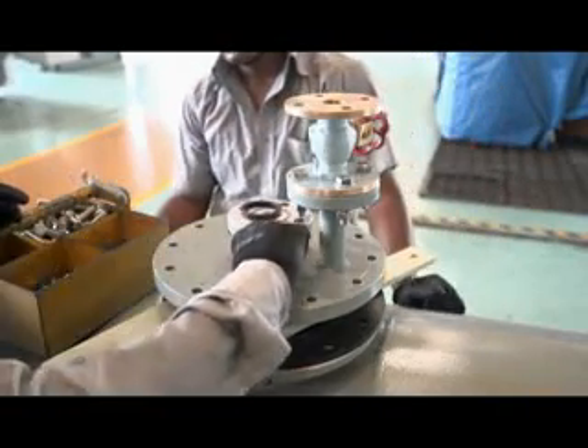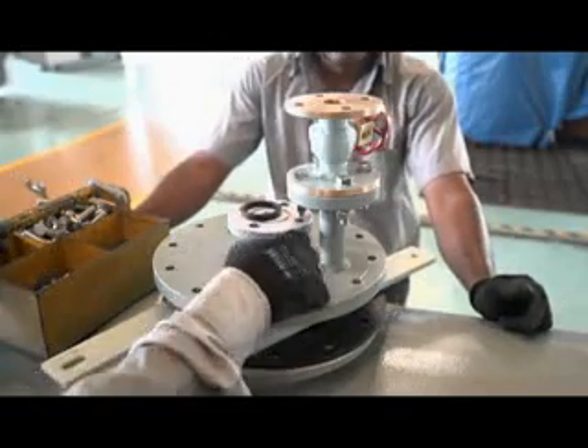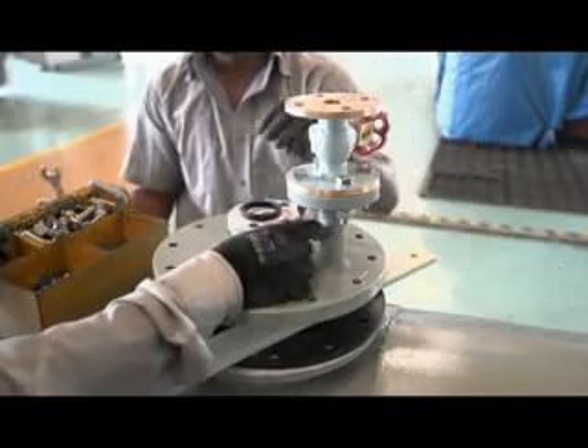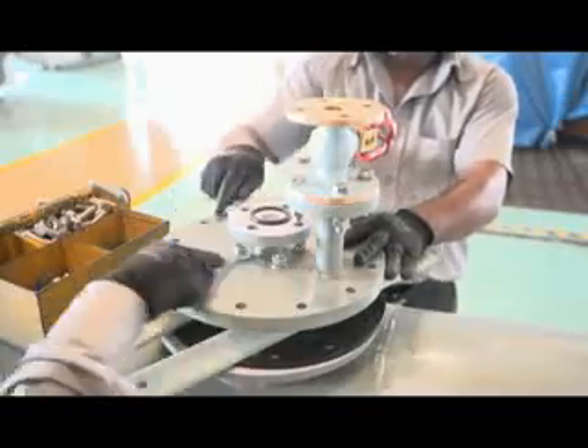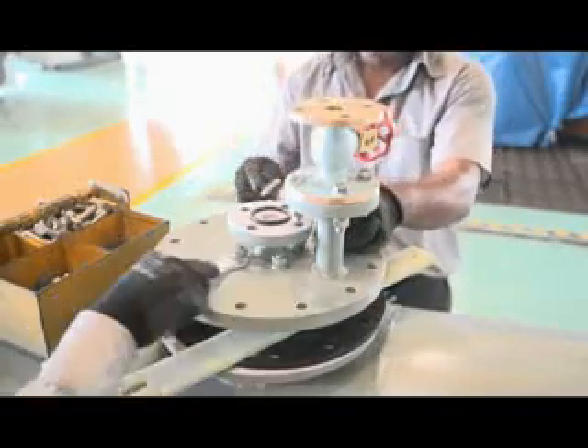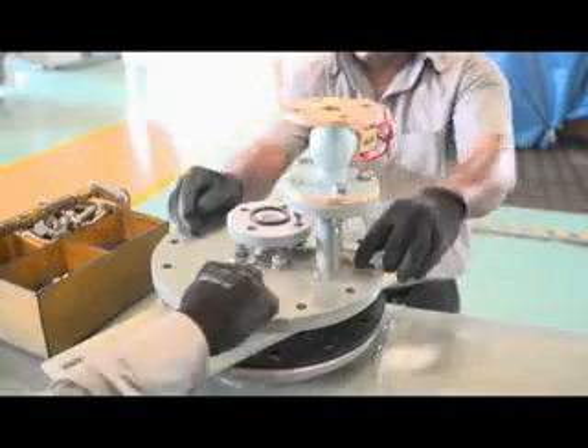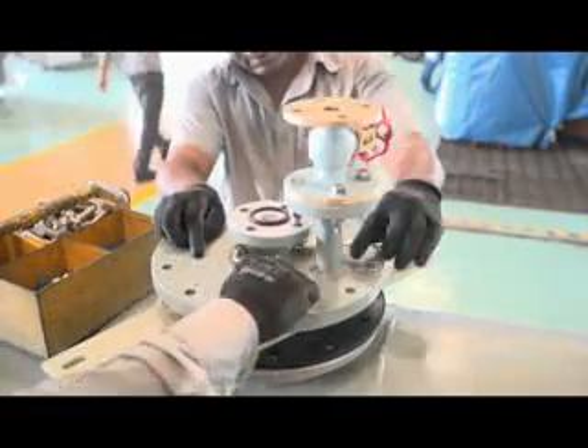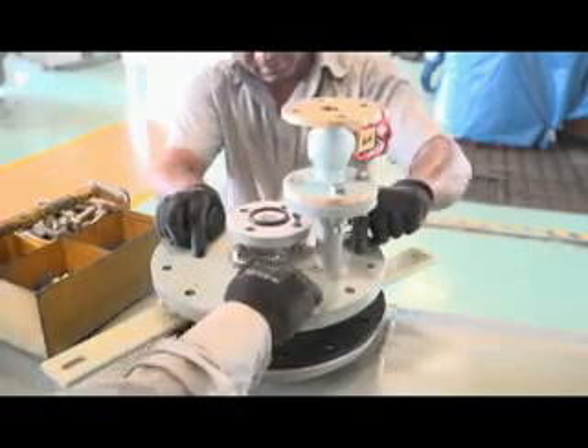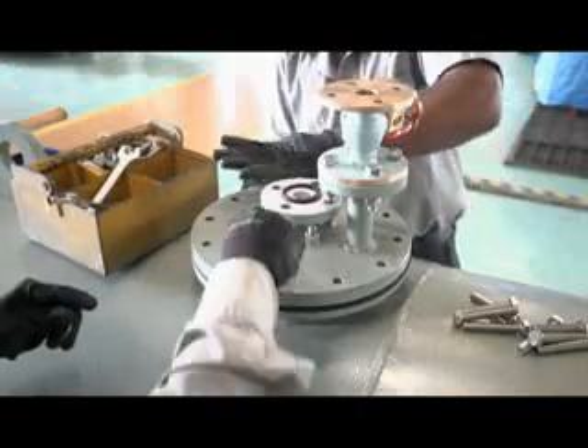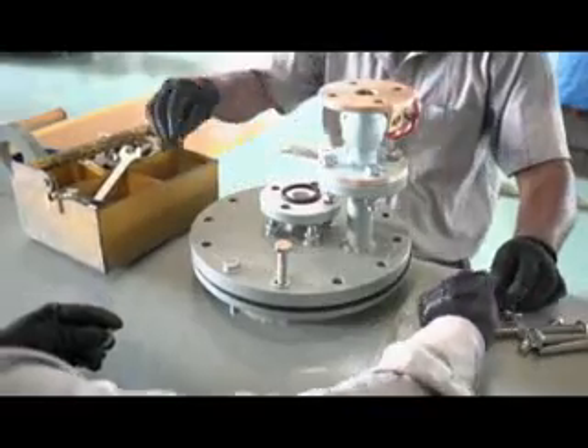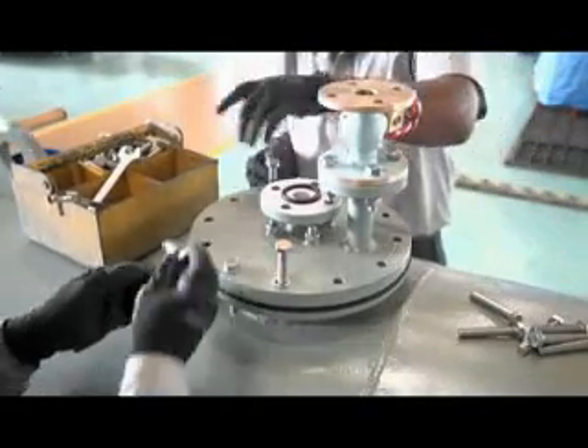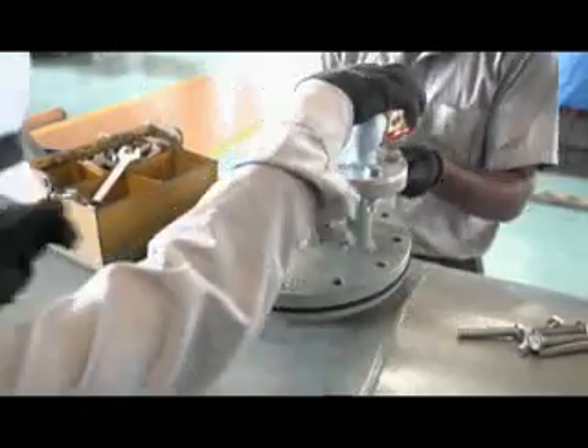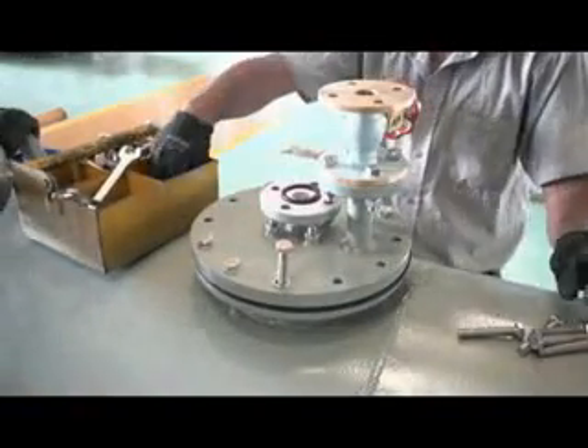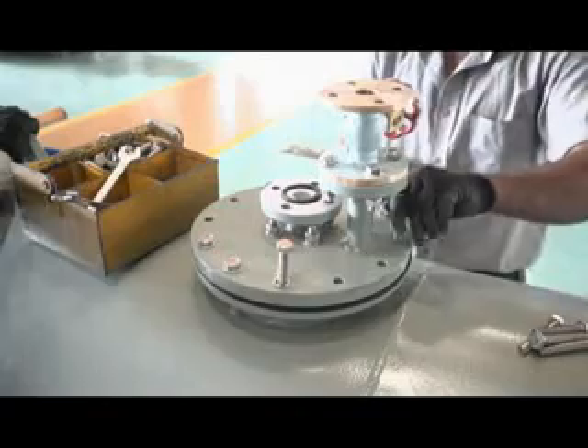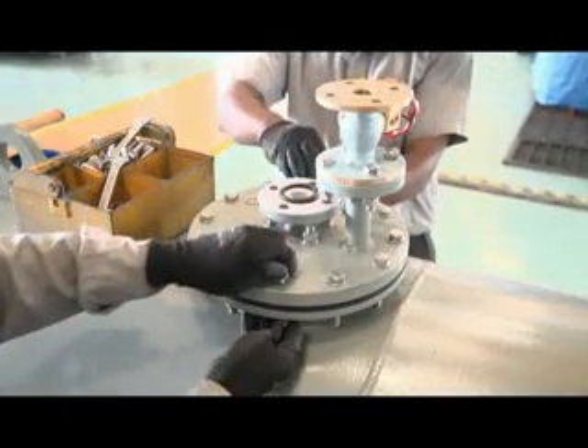The air cells are manufactured using a time-tested combination of nylon fabric and a thick coating of elastomers: acrylonitrile butadiene rubber, polychloroprene and Hypalon (CSM). The rubber compounds are formulated so as to minimize separator degradation and resist leakage of air through membranes, thus reducing the amount of air in the transformer oil. Over a period of time, this air or gas can reduce dielectric strength and thereby accelerate the aging of the insulation system. The advantages of the air cell can be well concluded from the facts.